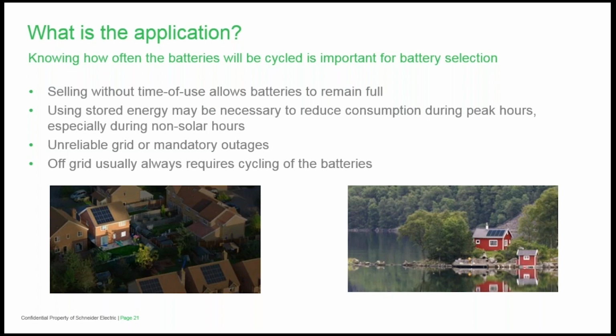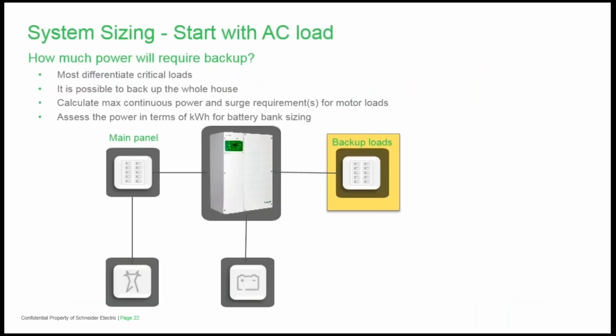If a customer wants to go off-grid, then cycling of the battery should be expected. Targeting state of charge percentage has been made easy with the Conext battery monitor and the Conext AGS. Typically, when we're looking at designing a system, we start with the AC load. So most are going to want to back up certain loads, although it's possible to back up the entire house, and many people do that, but that's going to require a larger system. So when we talk about maximum continuous loads, we also need to consider the surge requirements as well.